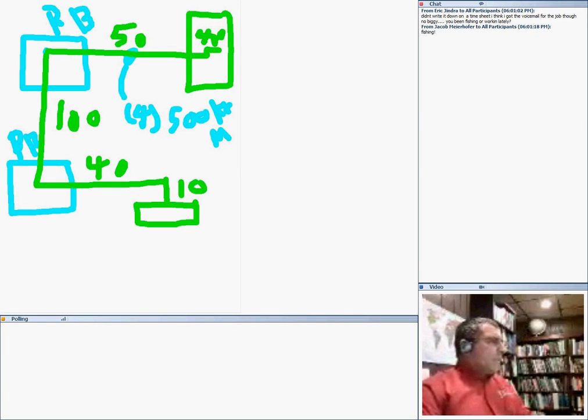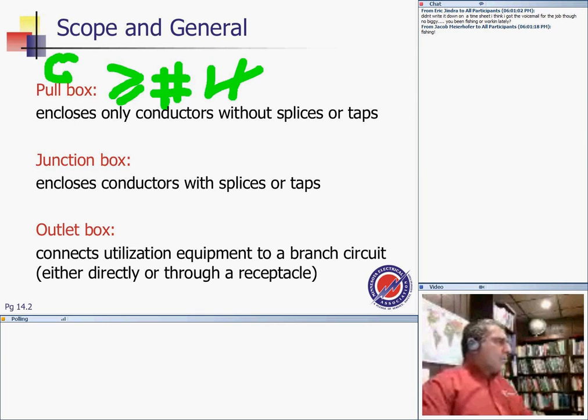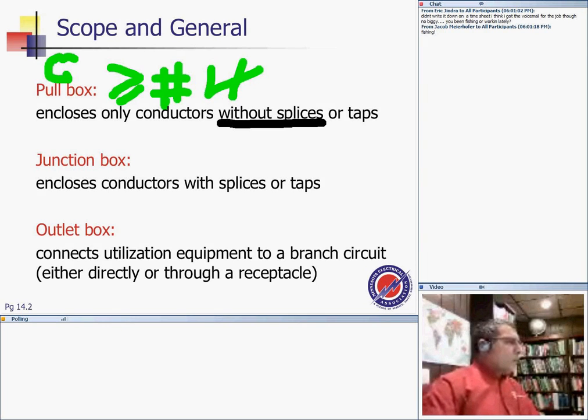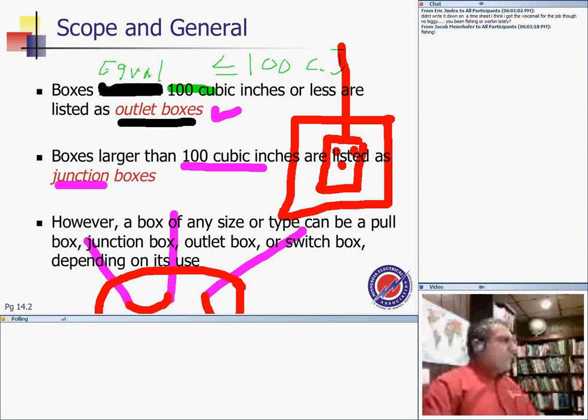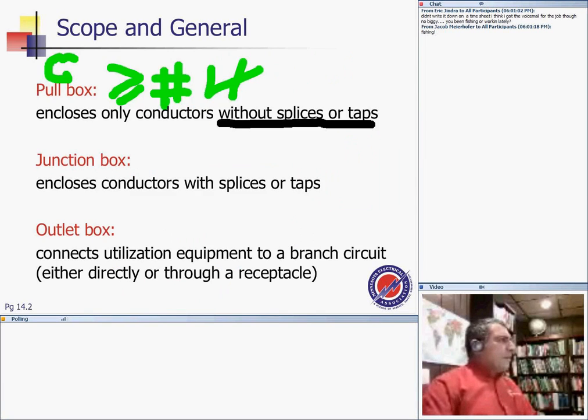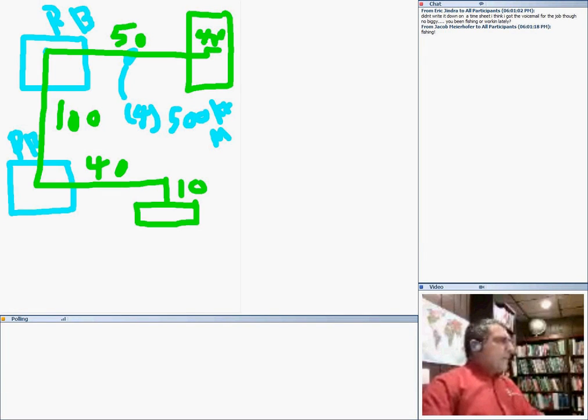When you have a pull box, you're dealing with large size conductors, number 4 or larger. And guys, without splice, that was true before. That was true until 2008, as a matter of fact. Now you can splice in a pull box. So what does that mean, Chad? It means, well, let's clear it up, and let's say the first run I came over here, and then I grabbed another run here, from here all the way up to here. Okay.